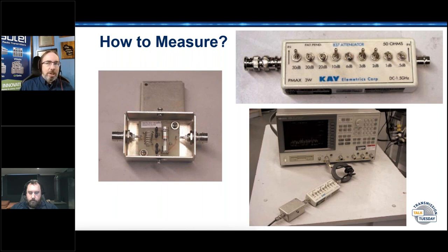That third harmonic should drop to minus 50. If it goes to minus 60 or 70, then you're overdriving the front end of your analyzer and you need more attenuation. By the same token, if you're working on a high power signal, attenuating the fundamental will help, and then you set your reference level to accommodate.